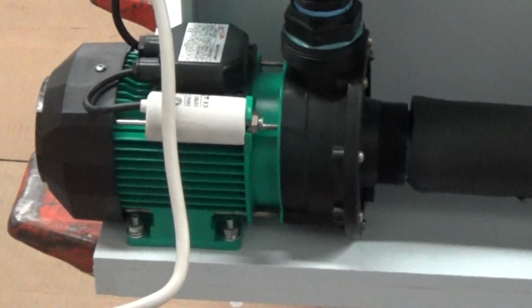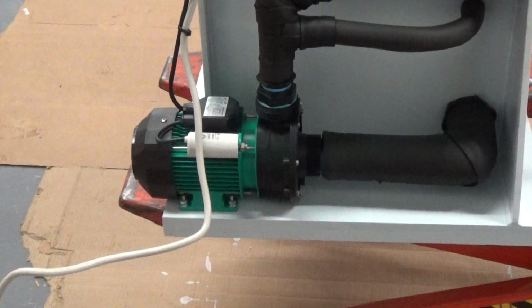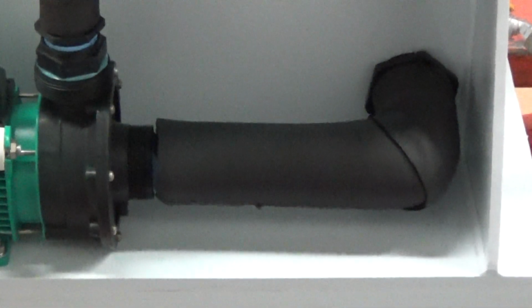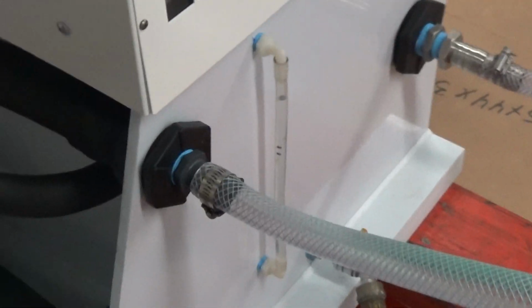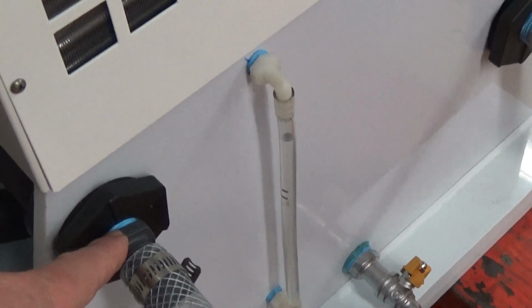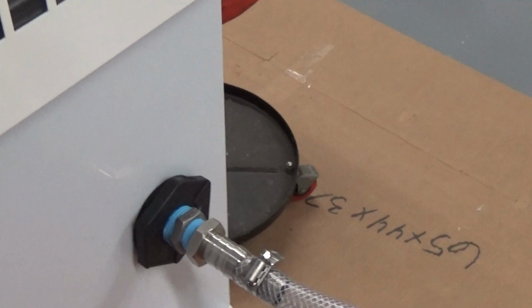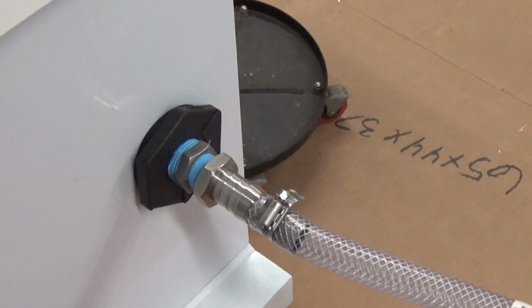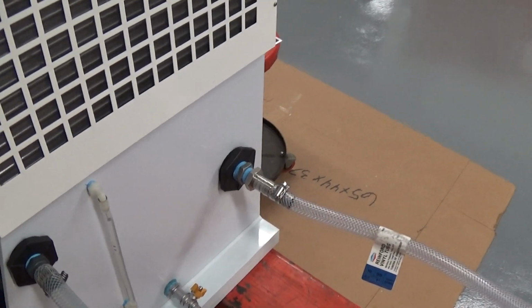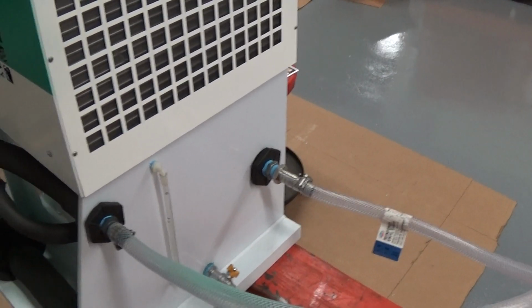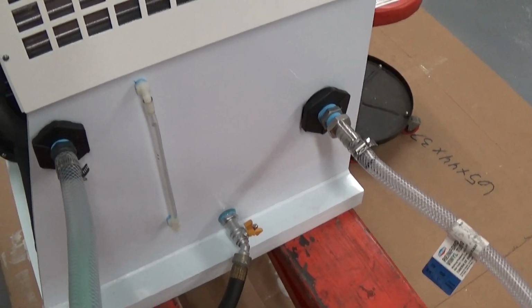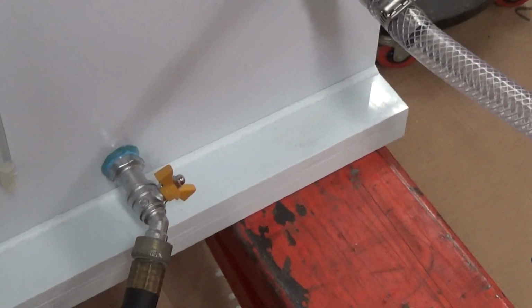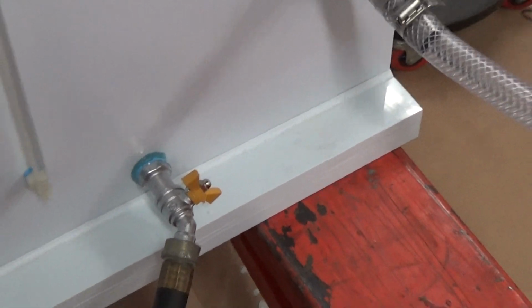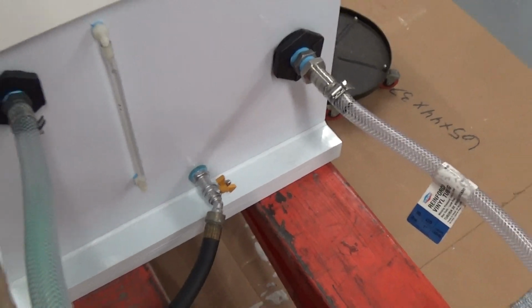We have a half horsepower centrifugal pump. That's your suction line, if you will, drawing from the tank. And then we have the discharge line that comes back here. Now in this unit we have a 3/4 inch NPT output and a 1-inch NPT input. We like to have the inlet back to the chiller slightly larger. We also have a sight glass here, and we have a drain which you can use to either pump in your fluid when you do fill, or if you ever do need to drain the fluid.